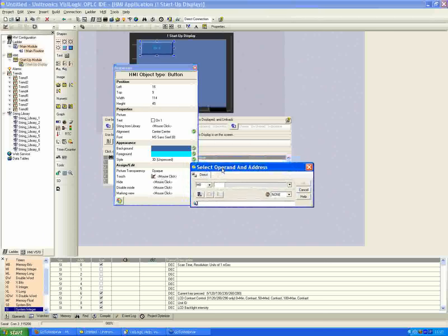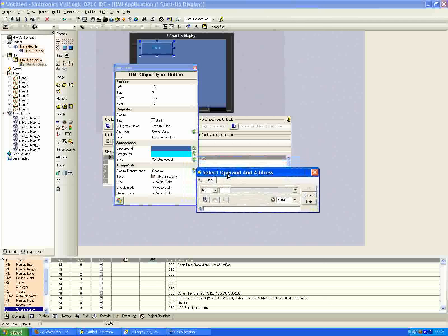The other important property to assign is the touch property. By default it's just a mouse click, which doesn't do much on the HMI screen, so we need to assign a touch property. Click anywhere in the mouse click area, and we have the option to select an operand and address. This is a push button — a Boolean value — working with our memory bit. Clicking the blue 'get next unused address' button finds the next unused memory bit, making it easier to avoid accidentally overriding one already used.